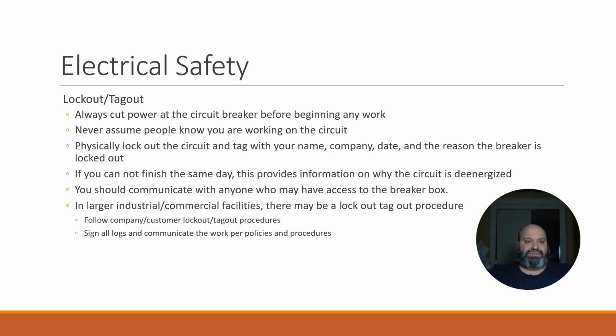You want to cut power at the circuit breaker before beginning work, but you also want to make sure other people know you're working on the circuit — don't assume others know. Communicate it, then put a lock and a tag so it's obvious someone is working on a piece of machinery attached to that circuit, so don't mess with it. It's called lockout tagout because you physically put a padlock on the circuit and a tag with your name, company, date, and reason the breaker is locked out. The information on the tag might differ based on state or local guidelines, along with company policies and procedures, but basically you're making it very obvious that you are working on this circuit — do not touch. The thing with lockout tagout is, if you're not finished the same day, this provides information on why the circuit is de-energized.